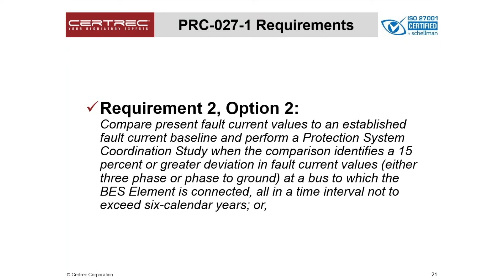Then for option 2, it's essentially getting a baseline fault current at your point of interconnection for a generator, and then comparing it over time to new studies, like year 2, you may have another study done, you want to compare it to that, and then year 4 and year 6. What you do is you compare your baseline to the new numbers. And if you get a deviation of greater than 15%, then you will need to do a coordination study at that time, but not to exceed 6 years.